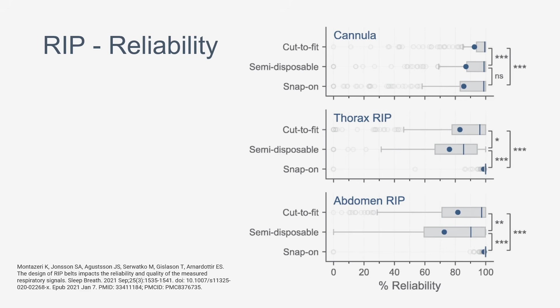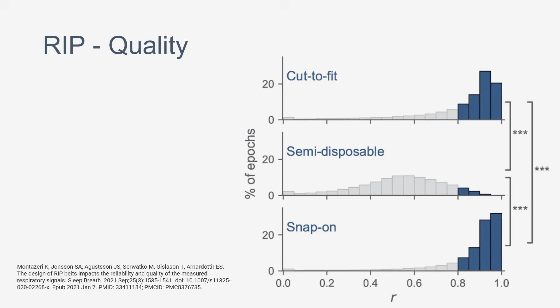And what we saw was that in the cut-to-fit belts and the snap-on belts, we had RIP signals that correlated well with the flow signal, and in the semi-disposable belts, there was very little correlation. So what we learned from this is that it's not only measuring RIP, which is important, but actually the quality and the design of the RIP belts really dictates the quality of the flow signal you get out.